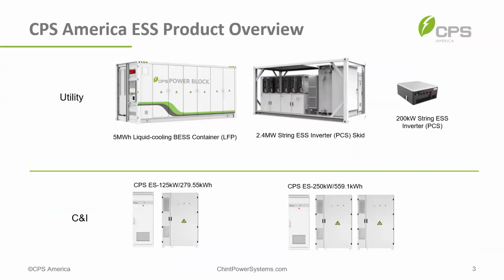So right here is essentially what we have for our battery offering. The top bit is going to be our 5 MWh BESS container, a 20-foot HC standard container. Then that 2.4 megawatt string skid is also 20-foot size, and that's going to be doing the DC to AC, AC to DC. That actually comes with a transformer on it.